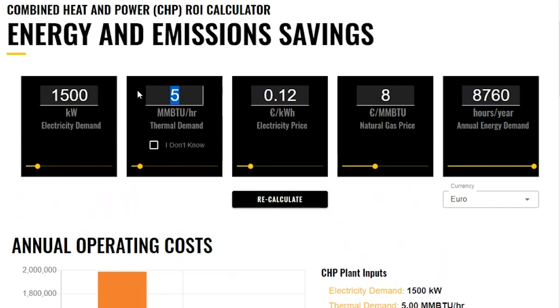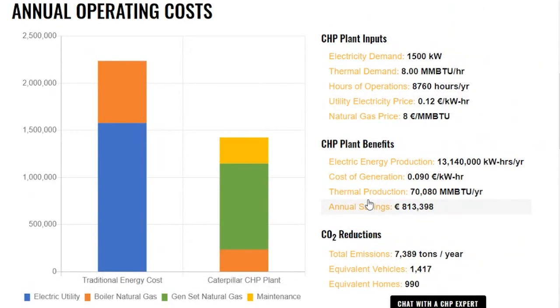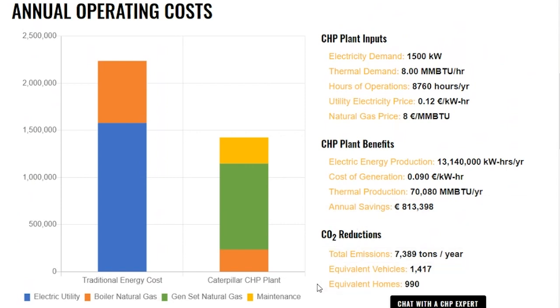Let's look at what happens if my thermal demand happens to go up at my factory. So my thermal demand is going to go up to 8 million BTU per hour and I'm going to recalculate. What you can see from this table is that now at my Caterpillar CHP plant, I have boiler natural gas required. What that's meaning is that the heat demand I need for my plant is more than what my Caterpillar genset can recover.